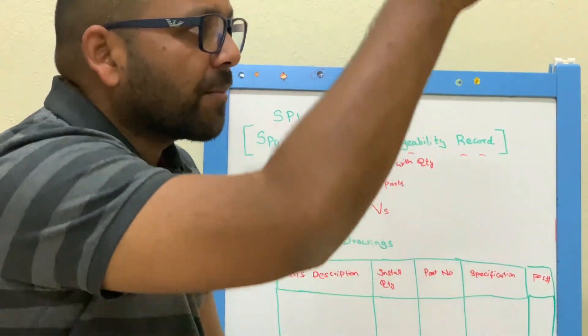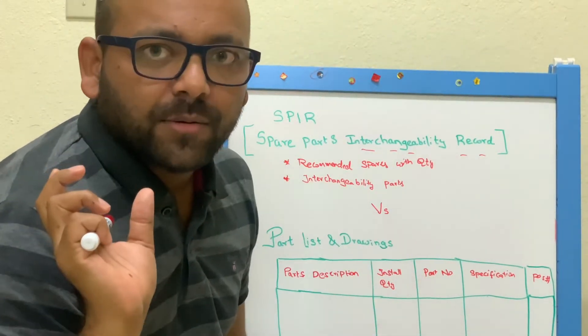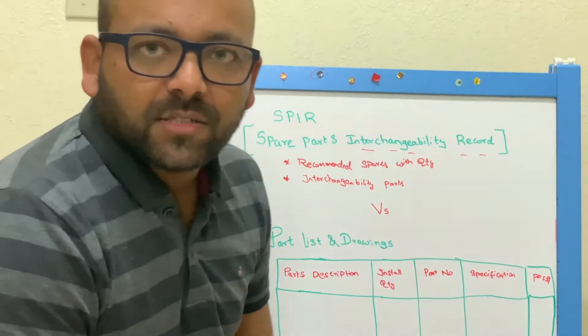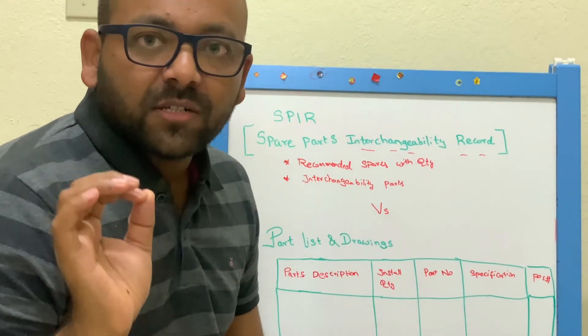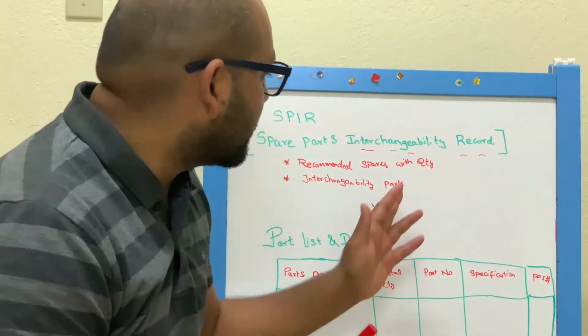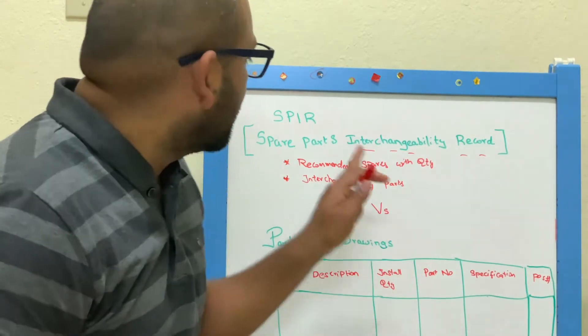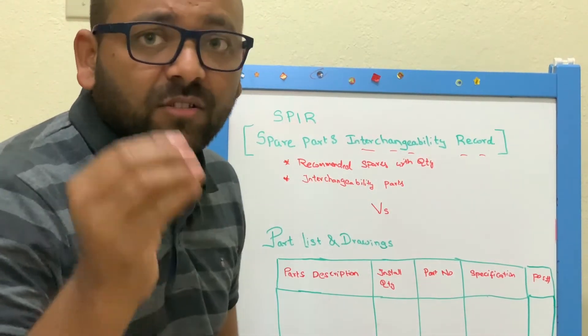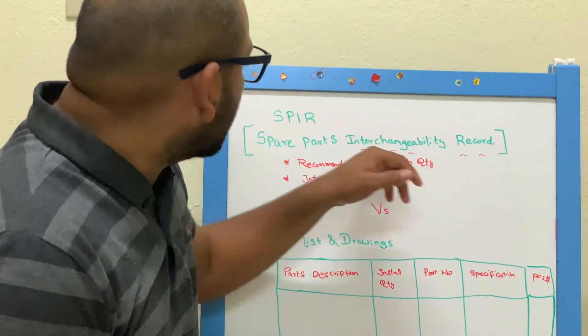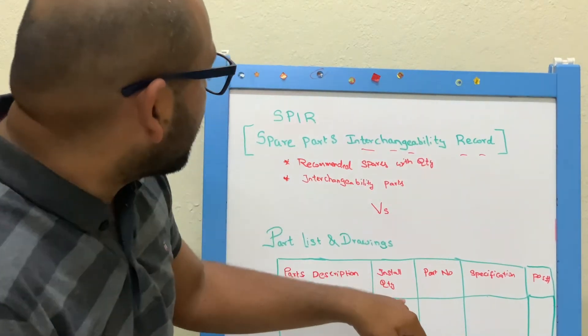You do not need to procure 100% of the quantity mentioned in the drawings. It is specifically indicated — if it is a minor inspection, go for bearings only or only mechanical replacements. If it is a major inspection, go for procurement of the complete shaft and all assembly parts. For example, the split-line bolts of the casing may have an install quantity of 120, 140, or even 200 — but the manufacturer will recommend the right proportion of what quantity is needed for the particular activity.